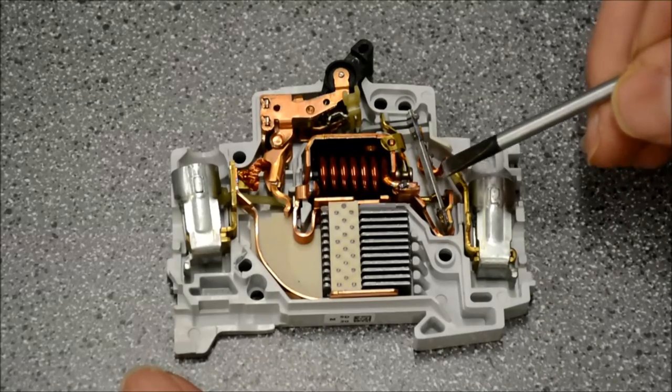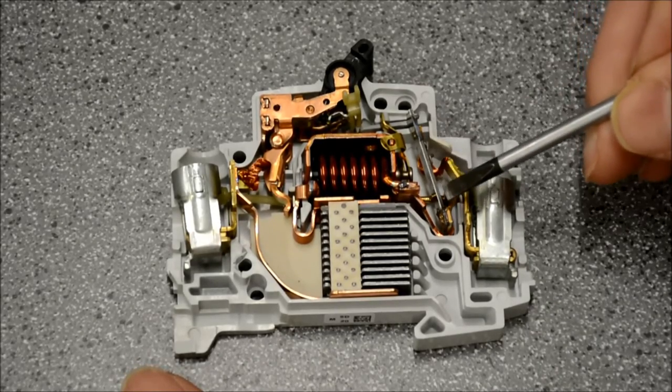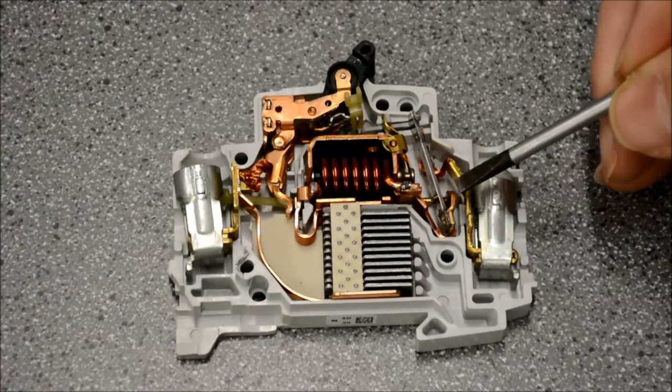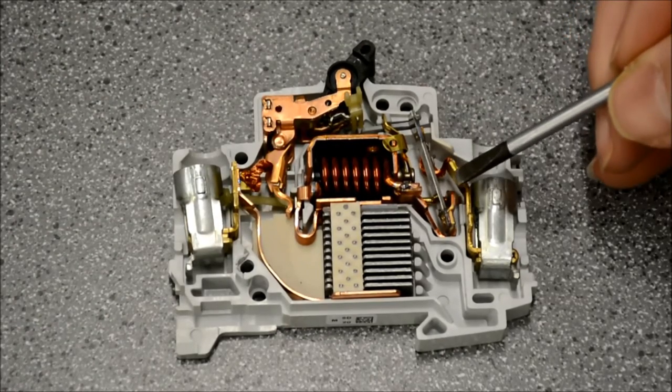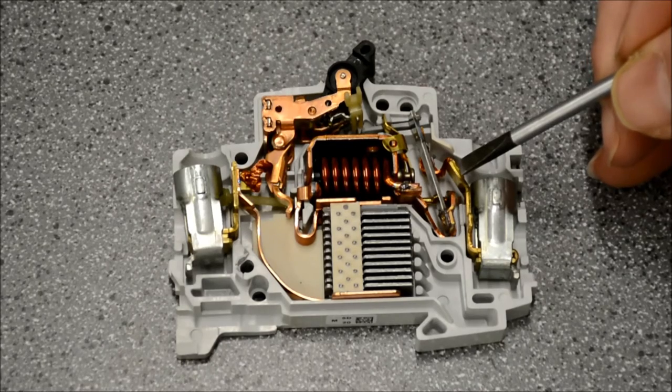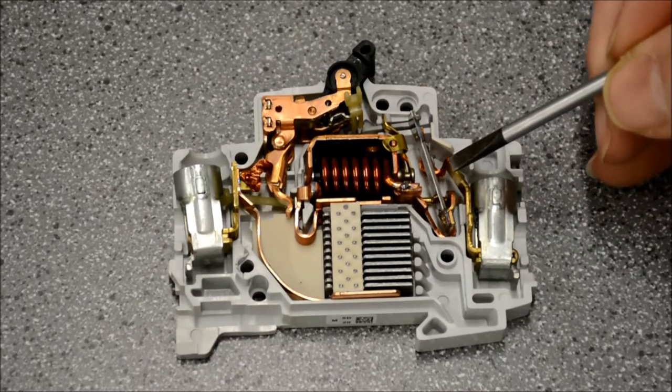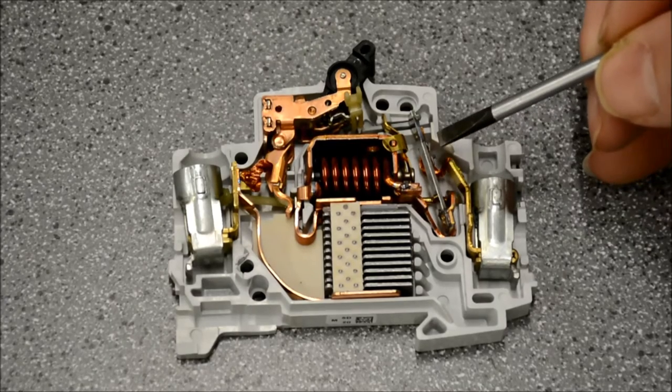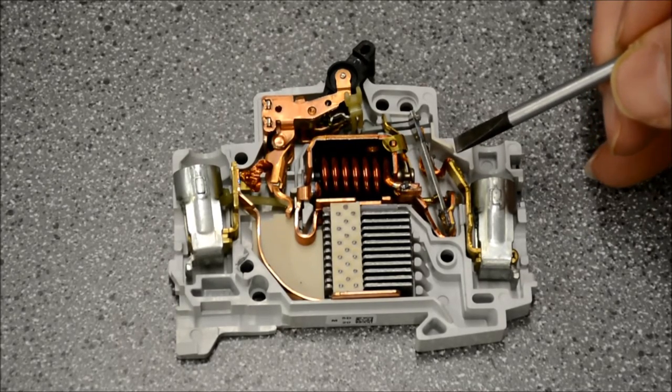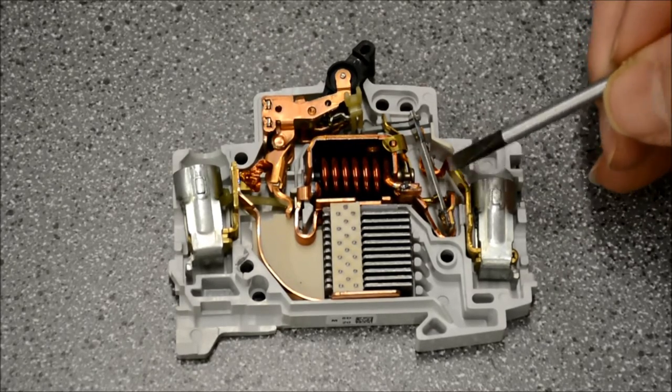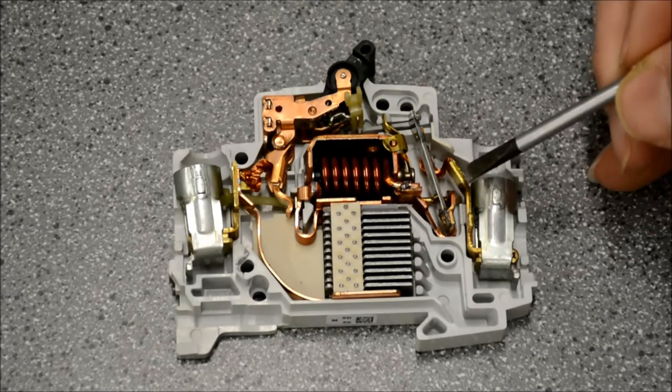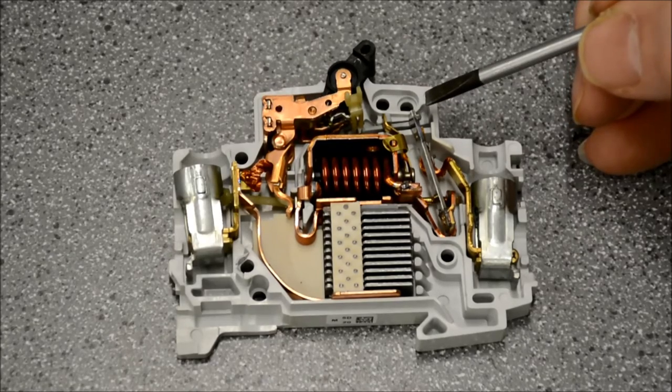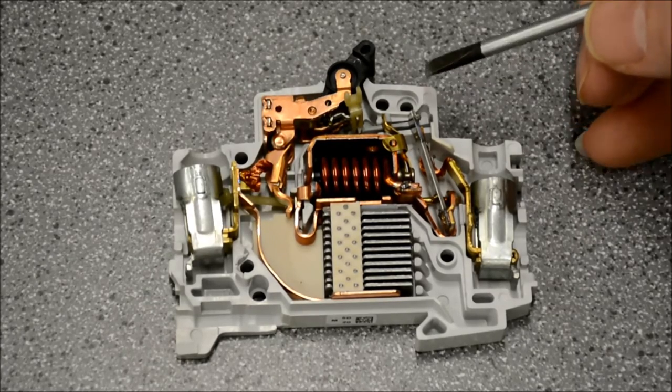Method number two is handled by this silver guy here known as a bimetallic element. Given its name, bimetallic, it is made up of two dissimilar metals that are bonded together. The important thing to know about a bimetallic element is that when it is heated, those two metals expand at different rates. Since they're bonded together, they tend to expand in a curved fashion, and we're able to exploit that principle to create motion inside the circuit breaker, which would lead to a trip.